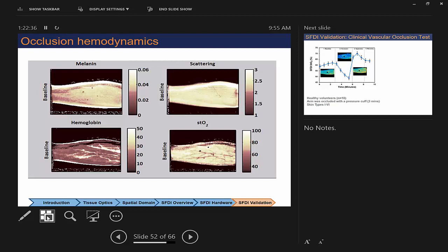I mean, it's a very non-quantitative way to say it, but if you're not correcting for scattering, you can get all different kinds of reflectivity from all different thicknesses of skin, from really thin skin on an older person to a really thick foot pad. But if you're measuring the scattering, then you know what that spatial scale of light transport is. You know roughly what the depth penetration of the light is, and then the absorption effects kind of layer on top of that. So in practice, we have lookup tables where we vary scattering and we vary the concentrations of blood and other chromophores in each layer.